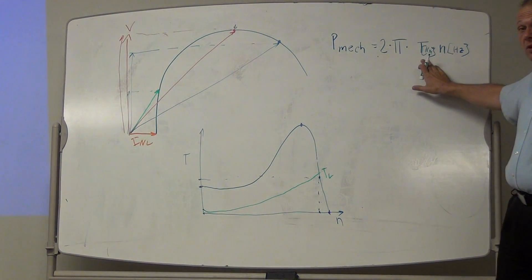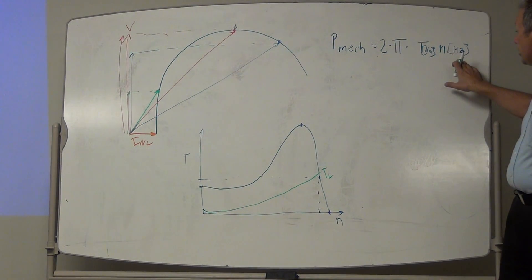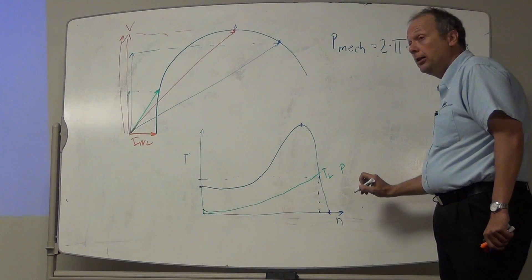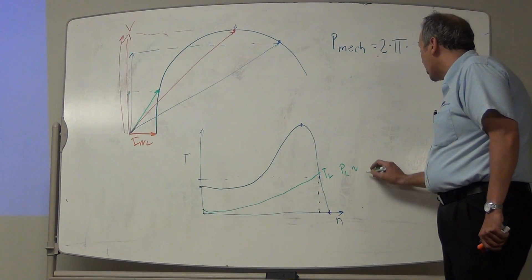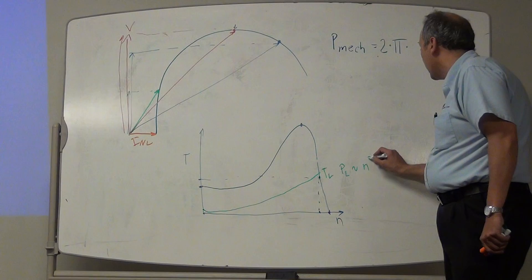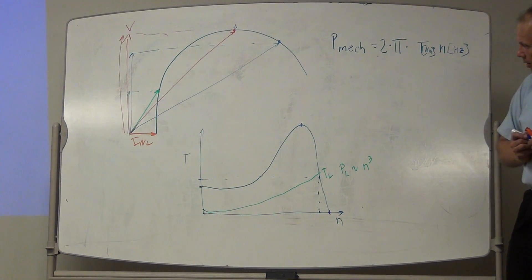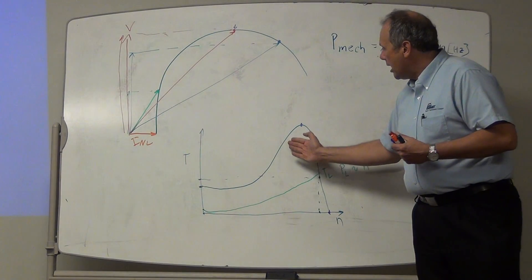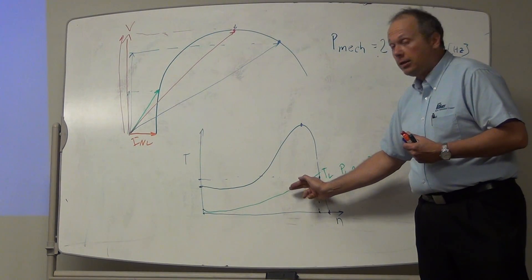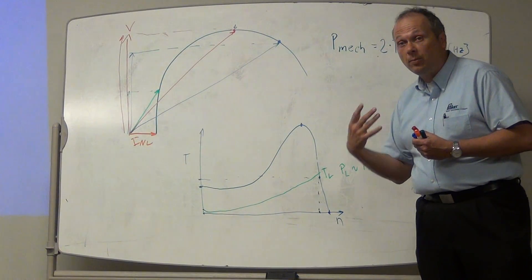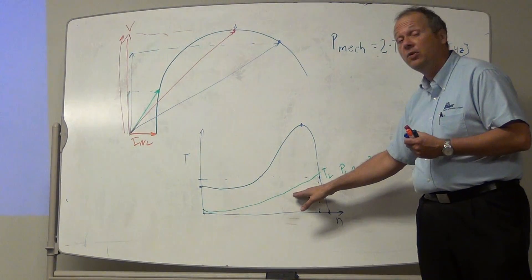That means that my power of the load is proportional to the cube of the speed, the third power of the speed. But now I need to relate the blue and the green. The blue is the capability of the motor, and the green is the requirement of the load.